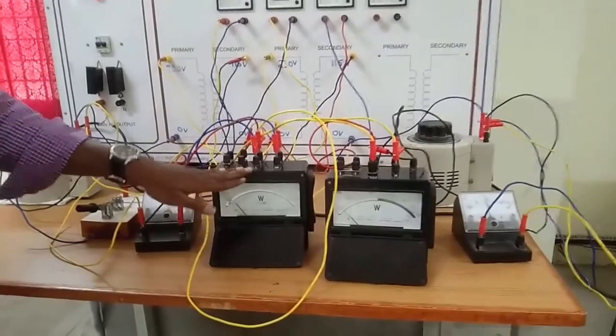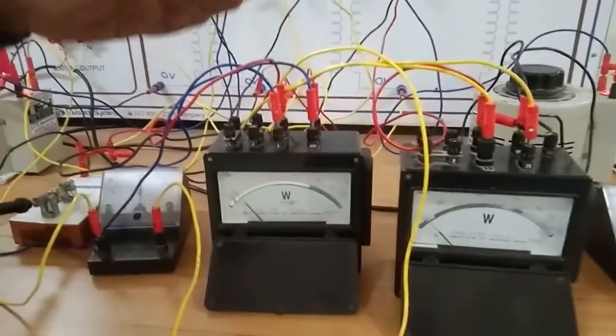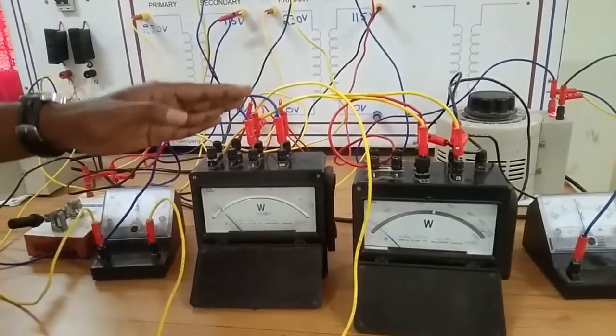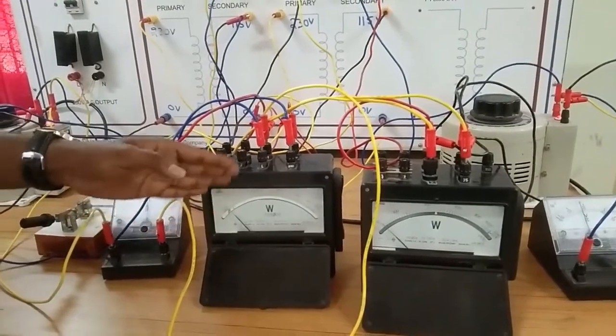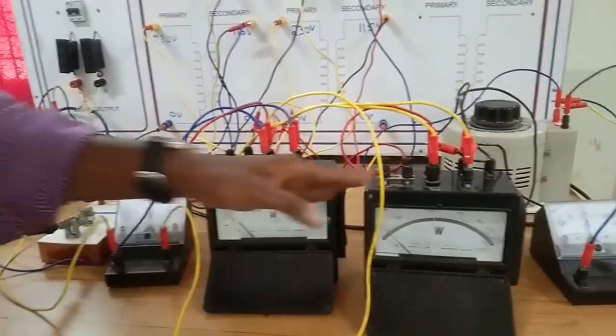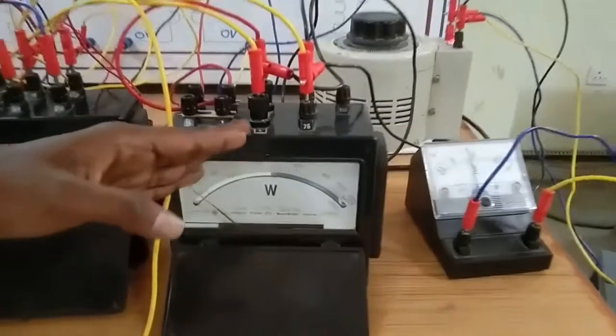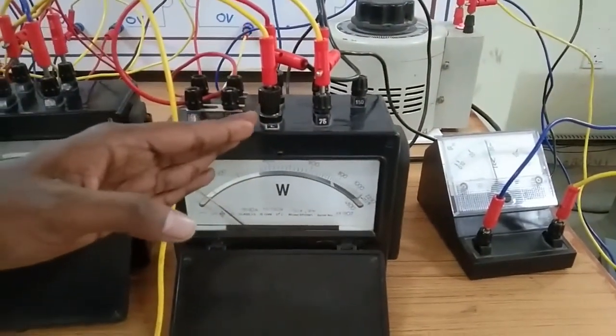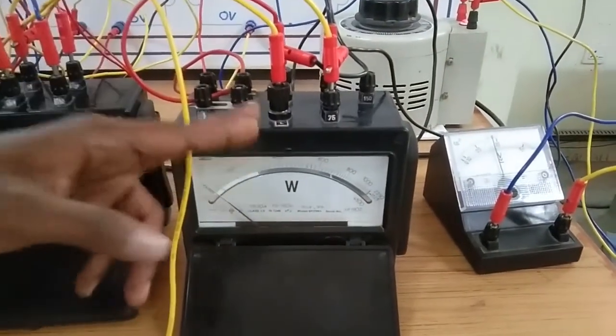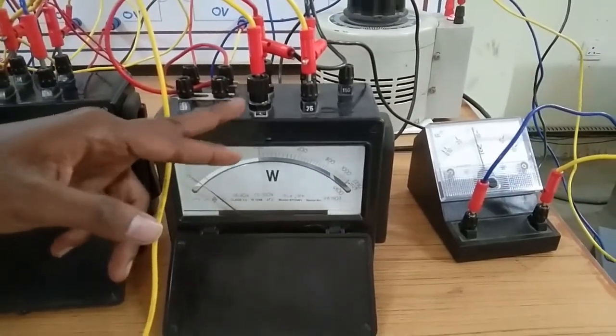First of all, we need to find the losses. This wattmeter shows the iron loss of both the transformers. So if you want to find the iron loss of an individual transformer, just divide by 2, right? You will get the iron loss of each transformer. In the same way, this wattmeter will indicate the copper loss of both the transformers. So if you want to find the copper loss of an individual transformer, just divide by 2.